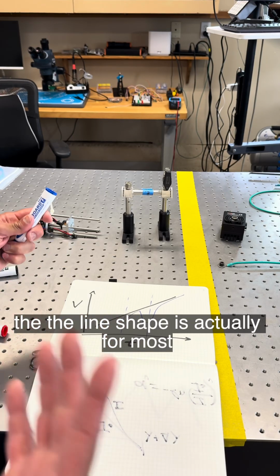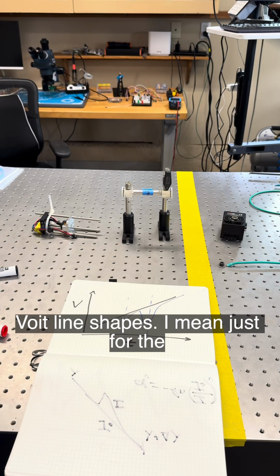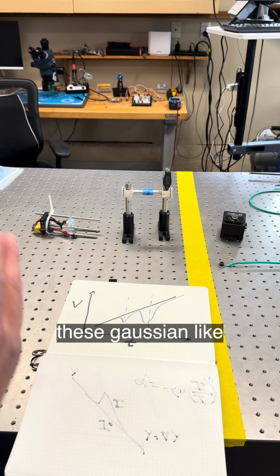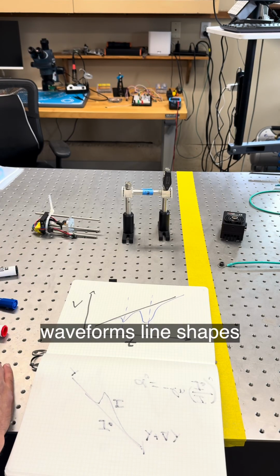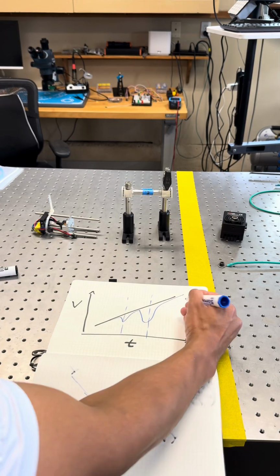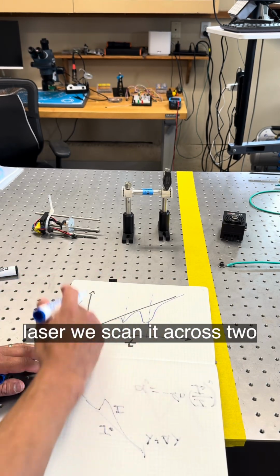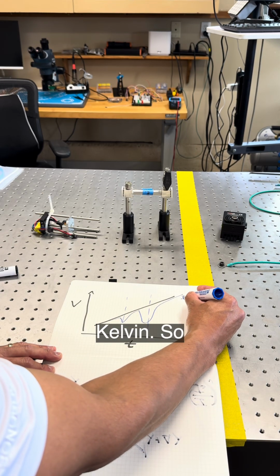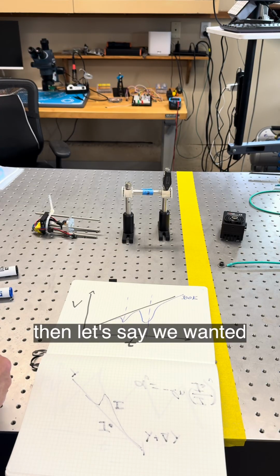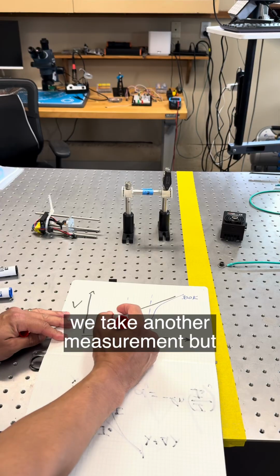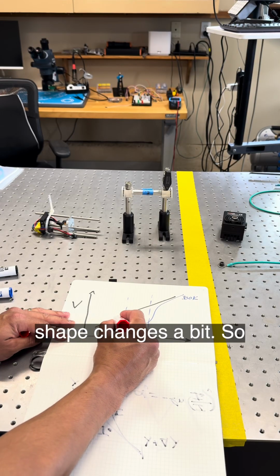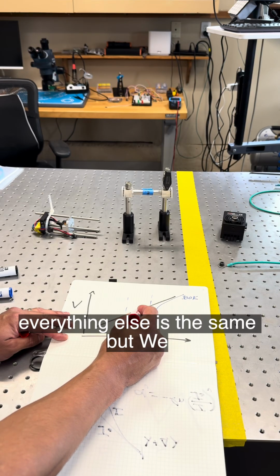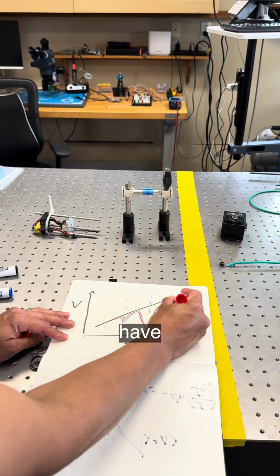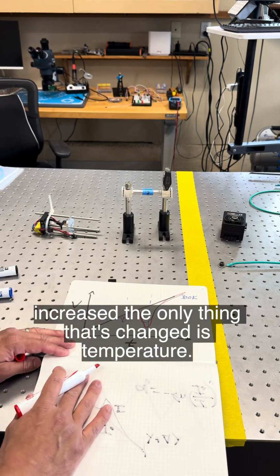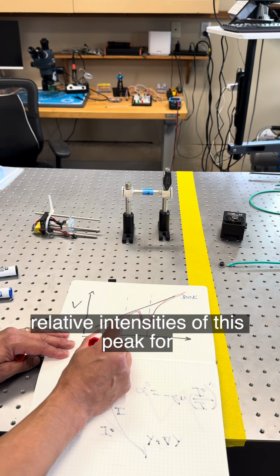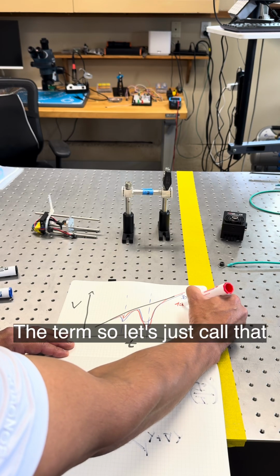The line shape is actually, for most purposes and for the purposes of this application, a Voigt line shape. Just for the sake of example, think of it as these Gaussian-like waveforms, line shapes. We operate a laser, we scan it across two lines, and the temperature is 300 Kelvin. Then we take another measurement, but now the line shape changes a bit. Everything else is the same, but the temperature has increased. The only thing that's changed is temperature. So you're going to get different relative intensities of the peak for each of these lines at a different temperature. Let's just call that 400K.